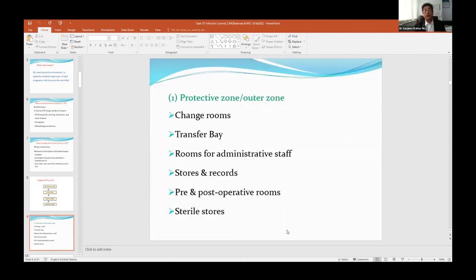The first zone, the outer protective zone, is where the changing rooms are. All these zones should be separated by doors, so that the air is separated from one zone to another. The change rooms, transfer bays, rooms for administrative staff, stores and records, and pre- and post-operative rooms are all located there.